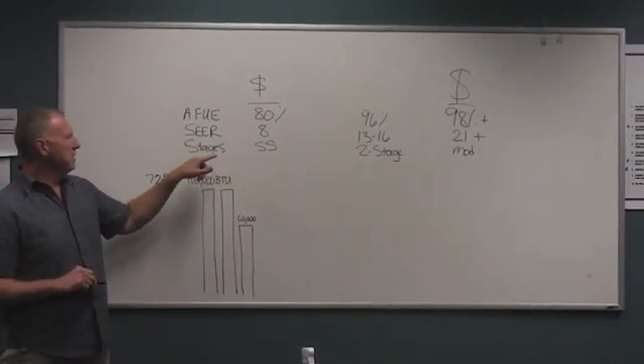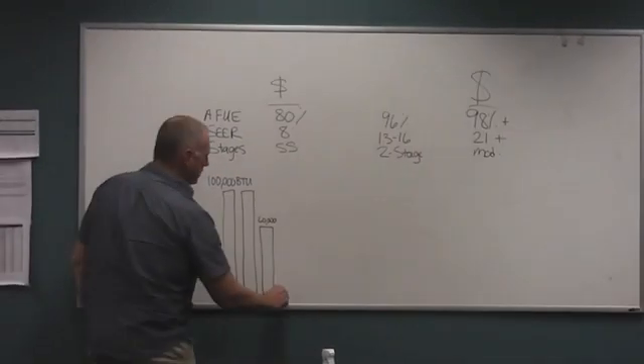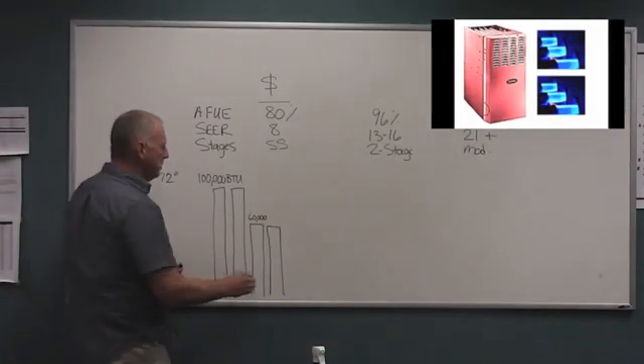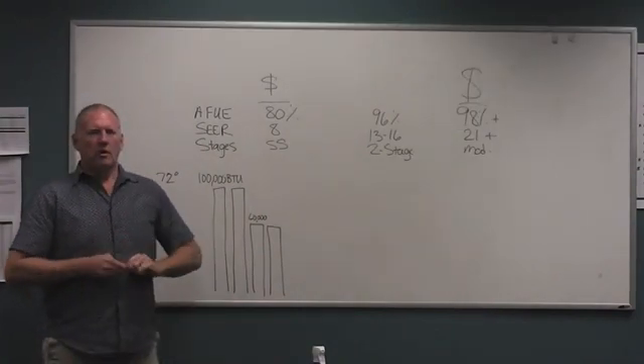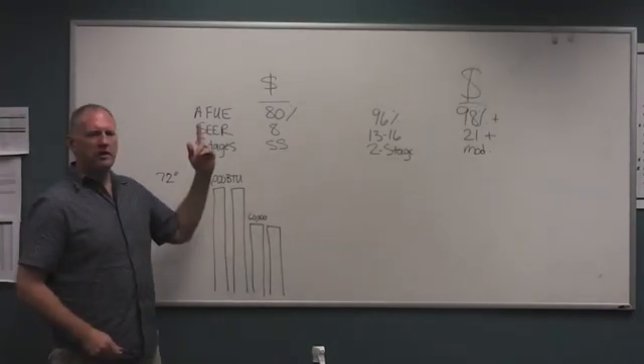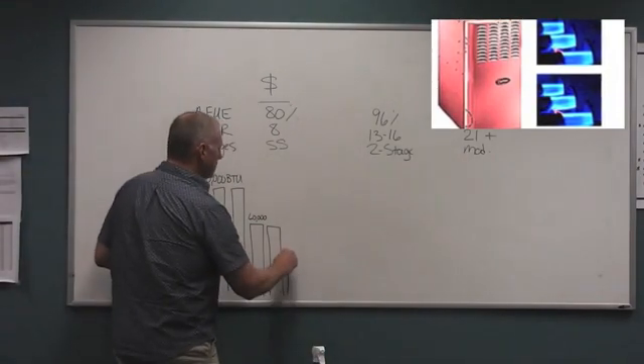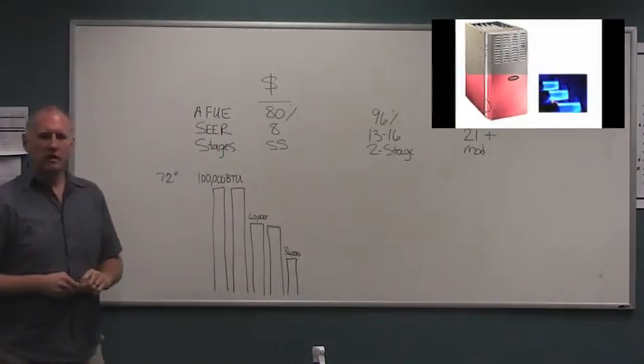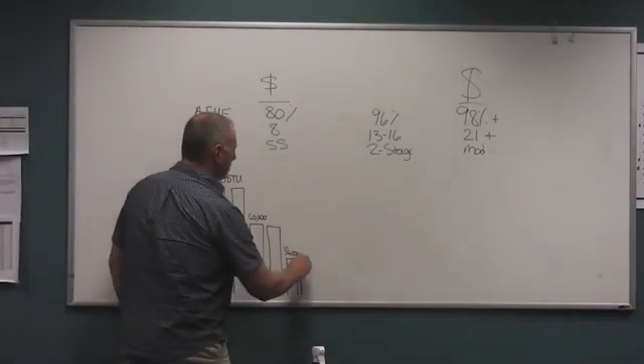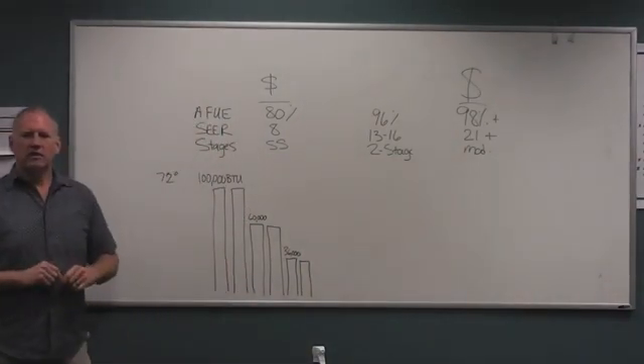I can put in a 60,000 BTU single-stage furnace that will just kick on and off as needed at 60,000 BTU. But if we go to a two-stage unit, this can actually save even more money because if somebody leaves the door open or you come home from work and it's cold in the house and you turn on that furnace, it's going to kick on to 60,000 BTU and heat the house up very quickly. But when you have those little fluctuations and you're just trying to maintain temperature, it can also kick on to a setting of 36,000 BTU. If you look at this, this is nearly a third of what you're spending right now. Most of the time your furnace is going to cycle at 36,000 BTUs. That's going to save you a ton of money.